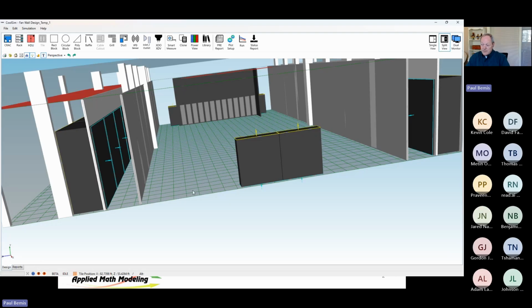And the issue here is getting enough air. Remember that we're looking at 125 CFM per kW. If you're going to put 40 kW in a rack of air-cooled IT, you need a lot of air. And so getting enough air in there has basically precluded raised floor. You really can't do it with raised floor anymore. The raised floor gets so deep because, again, velocity. We'll go back to the velocity, the Bernoulli issue. What happens is in a raised floor design, that underfloor velocity gets so high you can't get it out of the floor. It goes by where you want it to go.